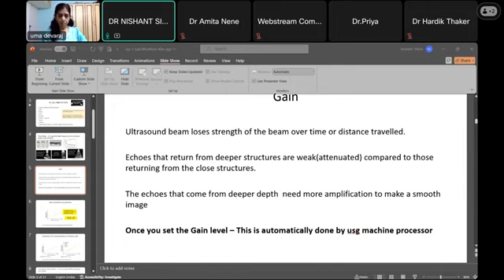So there's something called time gain compensation. It is a differential gain of each part of the image. So if you take 8 centimeter depth of your ultrasound beam, you can decrease or increase the gain at each level of your ultrasound point in the patient's body. So this is how it is. If it is at 1 centimeter, it will be a little less gain, but if it is at 3 centimeter, the gain will be more. So this is -1 gain at 1, but at 3 or 4 it is +1, +2, like that. So on and so forth, this machine can adjust. I'll show in the video about that. So this is a typical example of that.